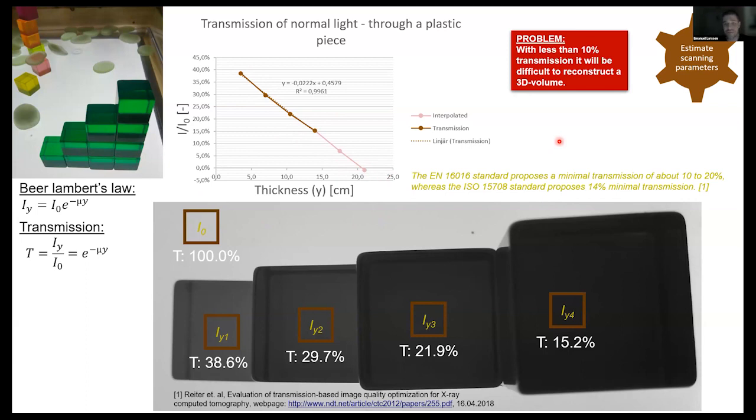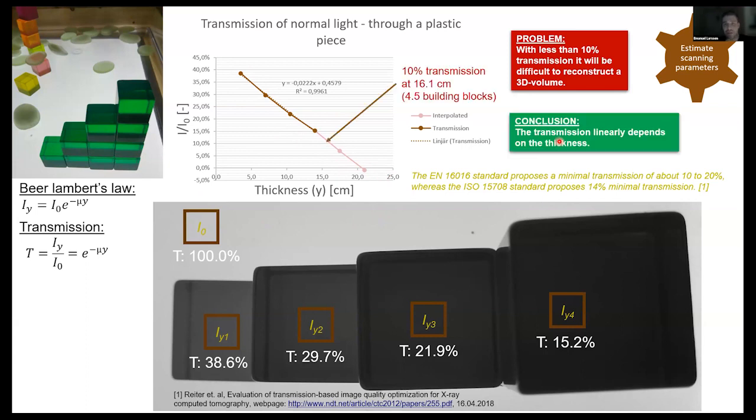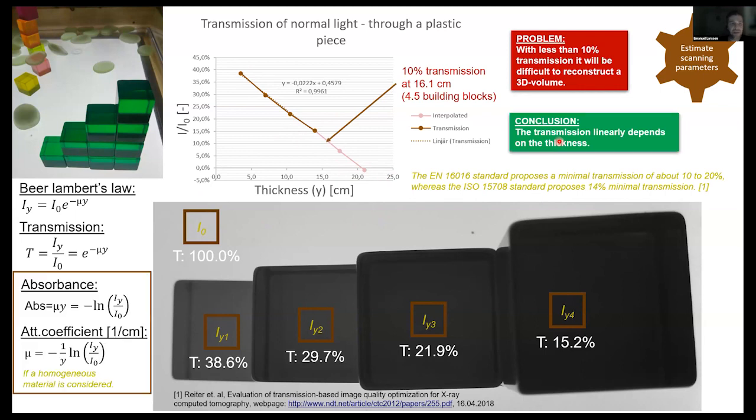And the things that we actually reconstruct in our images are the so-called attenuation coefficients. So mathematically, we first normalize the images, we create the sinograms, we back project, and then in the 3D volume is actually the so-called attenuation coefficients that we will have represented in a grayscale from, let's say, on a 32-bit scale.